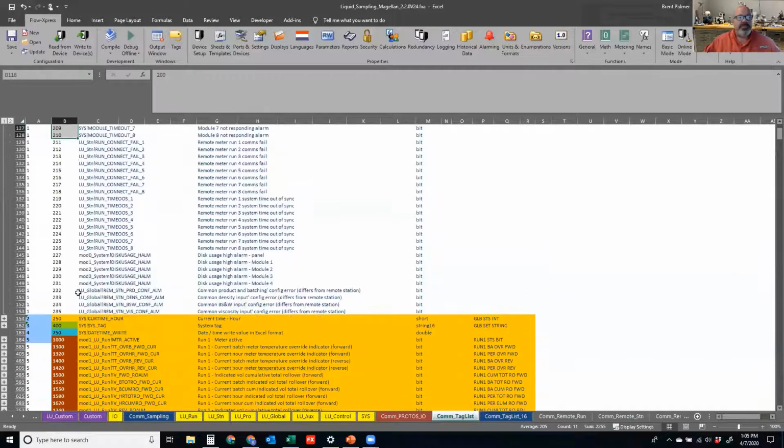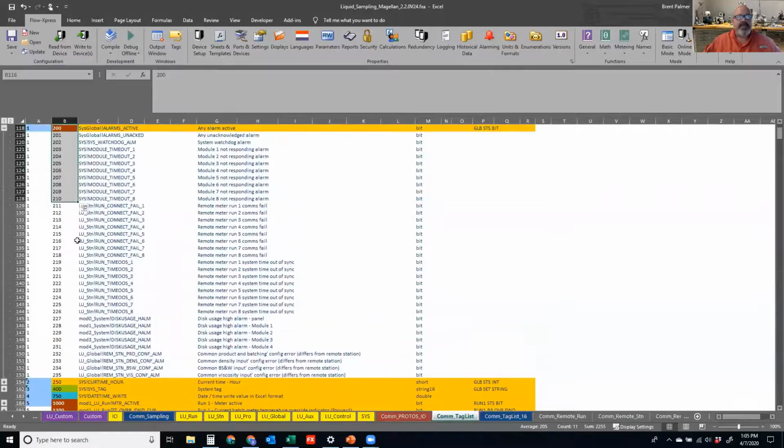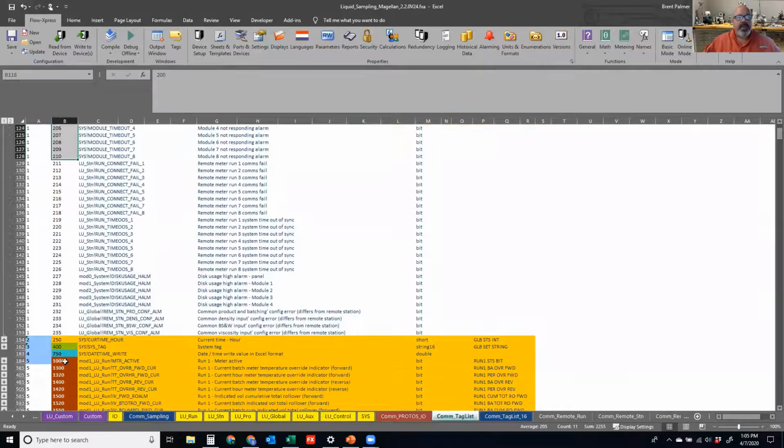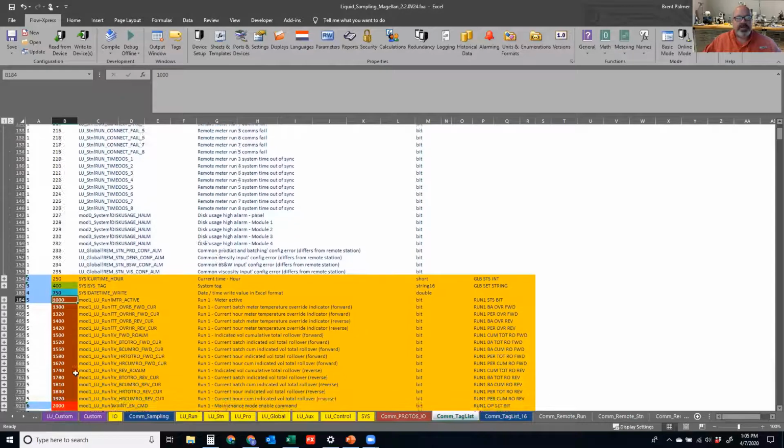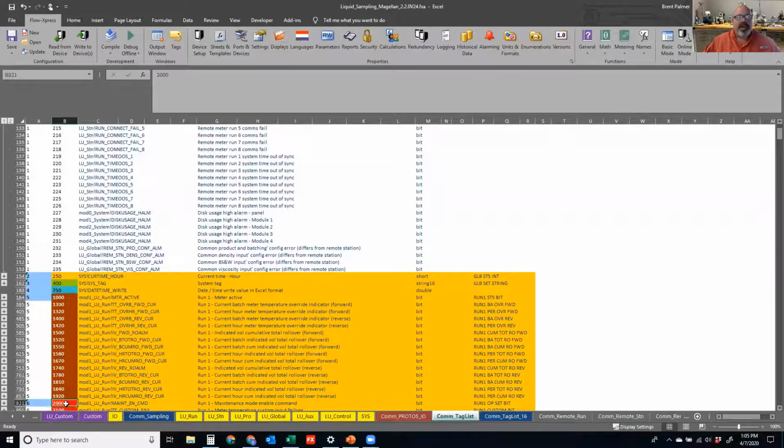But if I need registers 1,000, I can't say, well, in one poll, give me 200 and then also give me 1,000, starting at 1,000 for another 3. I have to create another poll or another query in the FlowX to poll register 1,000 for how many it wants. And then if I wanted to poll what's in the 2,000s, I have to create a third query and so on. So I'm going to show the difference between a slave sheet and a master sheet when we're actually setting something up to poll or when we're being polled by something.